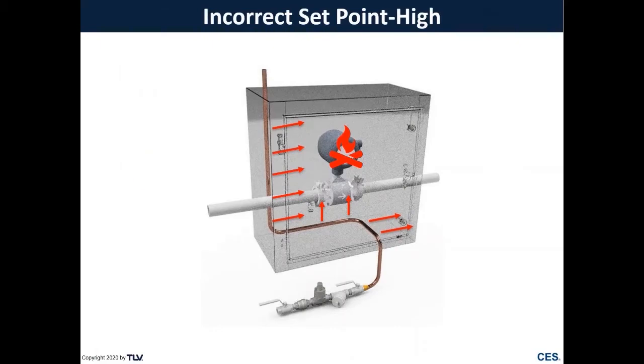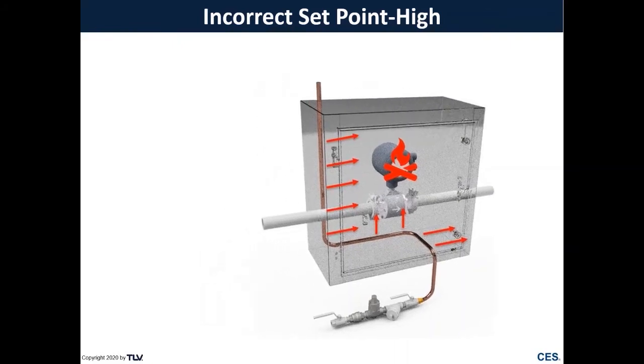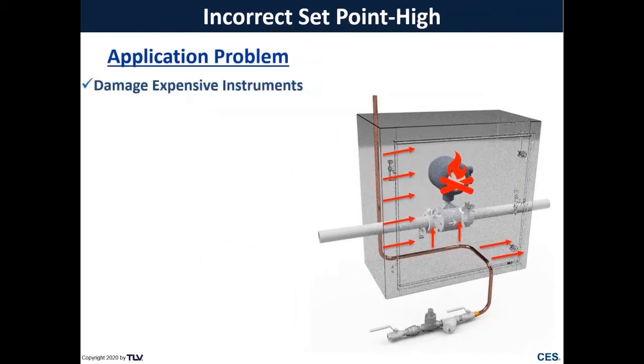Next is an incorrect set point that is too high. In an instrument enclosure with a tracing line, the purpose is to keep instruments warm and prevent freezing. But if your temperature-adjustable steam trap is set too high, you'll give too much heat into that enclosure, potentially damaging expensive electronics and causing process issues. This can also cause a shorter steam trap service life due to steam leaking through.